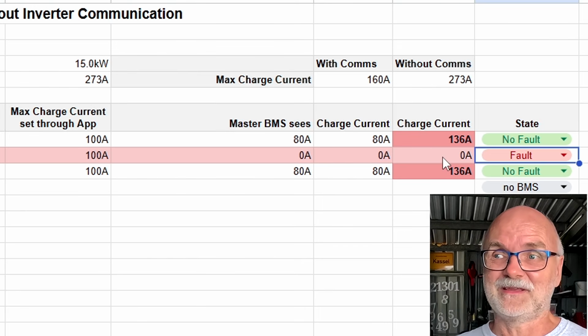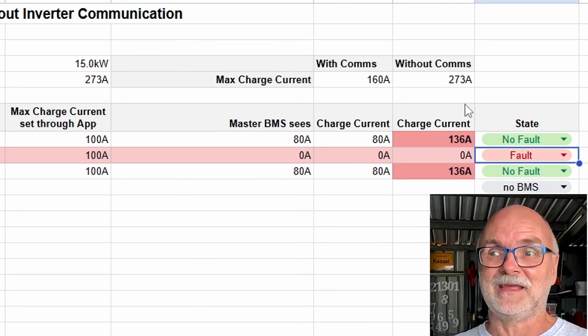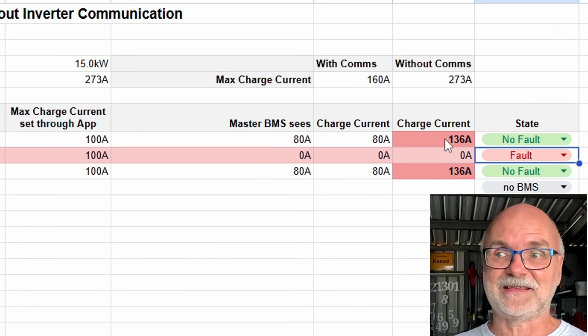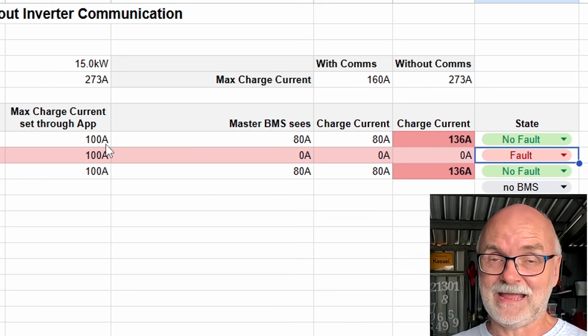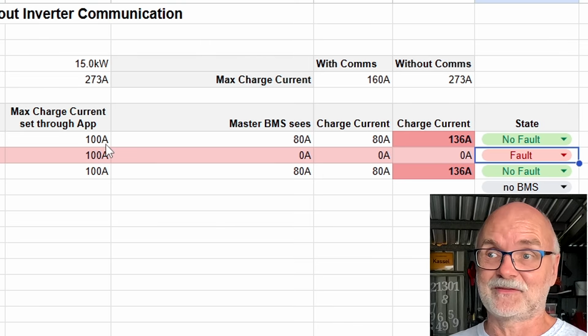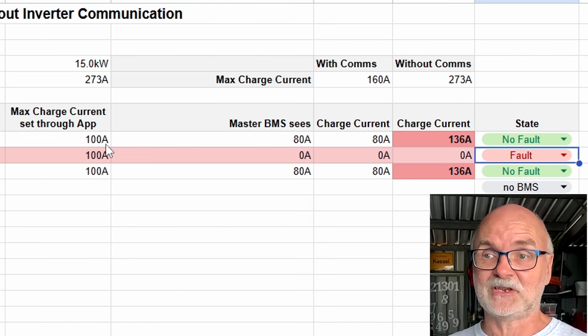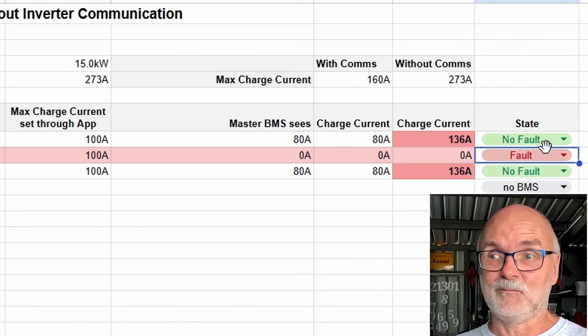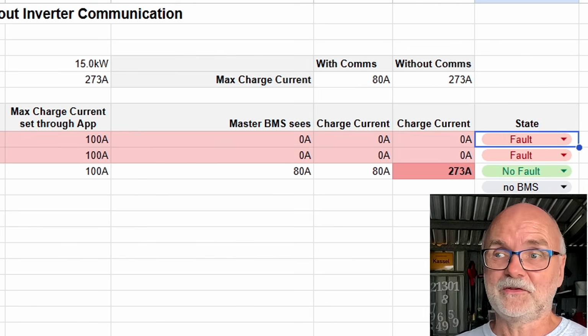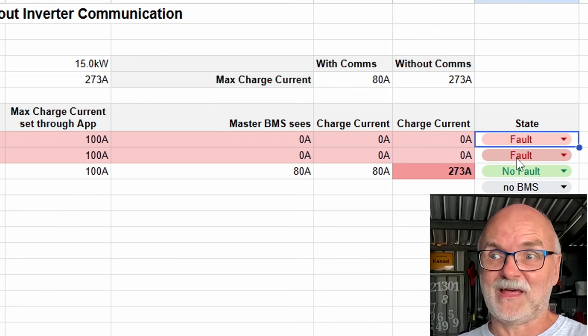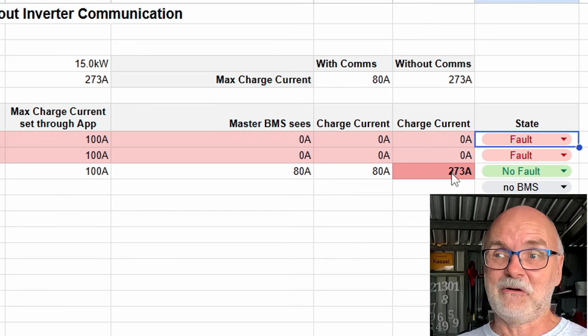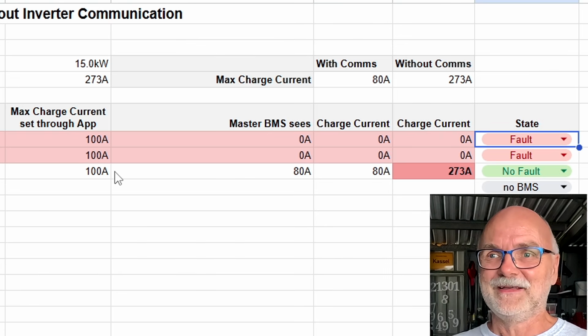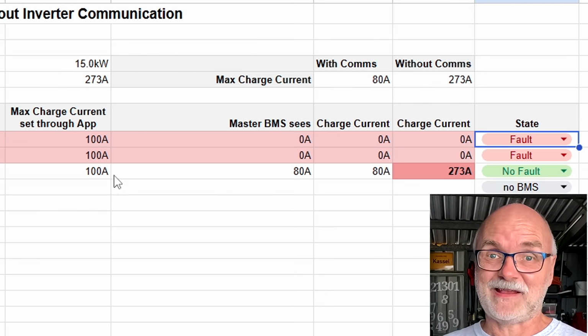This one trips out and your 273 amps coming in are now divided between the 2 remaining batteries, and you're getting 136 amps into these 2 batteries each. We have set 100 amps as the maximum charge current in your BMS. So you will trigger an overcurrent protection in these 2 BMSs. So one of them will trip first, fault. We've got two faulty, one with an over temperature, the other one with an over current now. And you can see now the remaining 273 amps going into one battery, and this is far more than the BMS can handle and your set maximum charge current is.